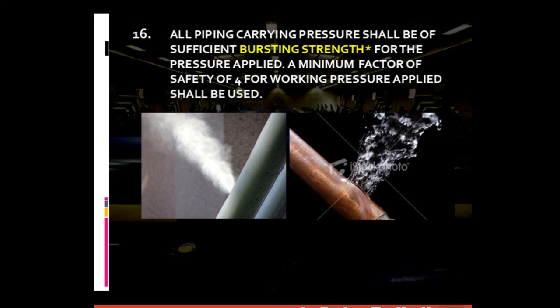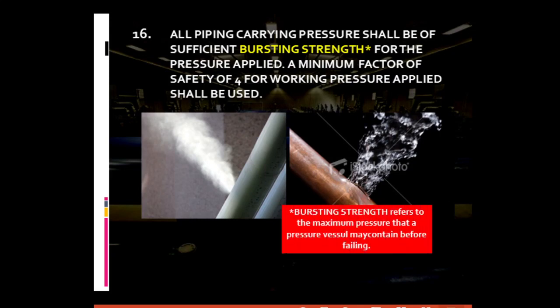For general piping requirement number sixteen: all piping carrying pressure should be of sufficient bursting strength for the pressure applied, with a minimum factor of safety of four for the working pressure applied. Bursting strength refers to the maximum pressure a pressure vessel may contain before failing. Once the kind of fluid to be conveyed is identified, the pipe material should be of sufficient bursting strength to withstand the pressure characteristic of that fluid, as specified in the PSME code.